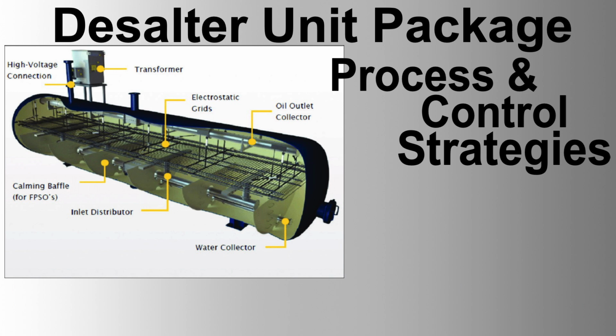3. Cascade control for separator inlet. Primary controller monitors the level in the three-phase separator. Secondary controller adjusts the inlet valve based on signals from the primary controller to maintain steady levels. From three-phase separator to electrostatic desalter.